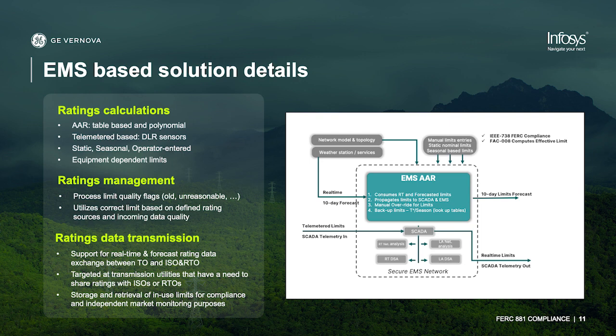So a little bit about how the application works. It has a feeder of incoming rating sets. So these ratings can be manually entered operator ratings. They can be, like I mentioned, the telemetered, which would be your digital dynamic line ratings from our GE applications, or field-based digital dynamic line rating applications, your ambient adjusted rating table, et cetera. Basically, it's looking at the hierarchy of controls of those different rating sets, and based on the telemetry or data quality, it's going to pick the highest priority with the best data set and put that rating set into effect, and then drive that rating into SCADA and all of your network applications to make sure that you're always operating to the most correct, best quality data of your ratings.